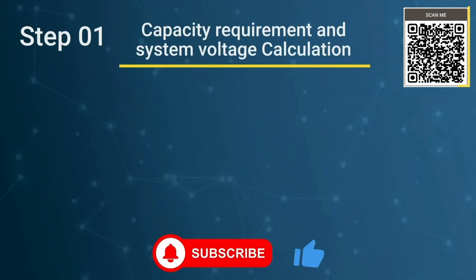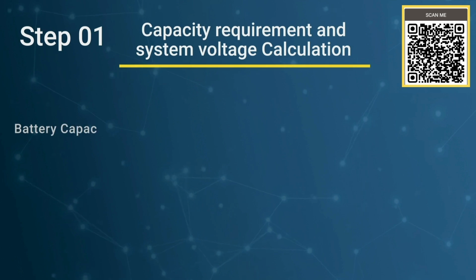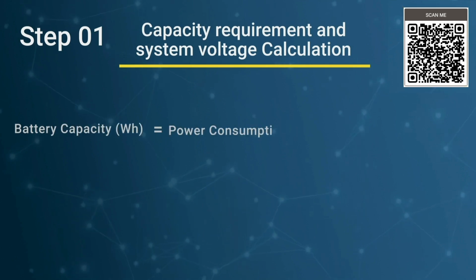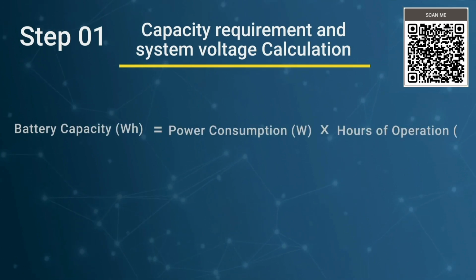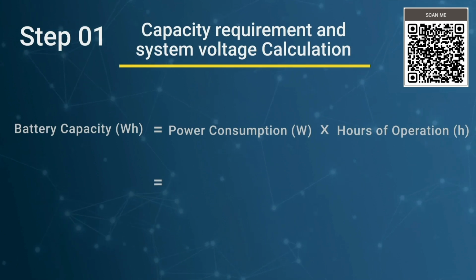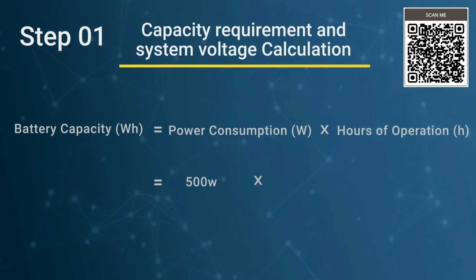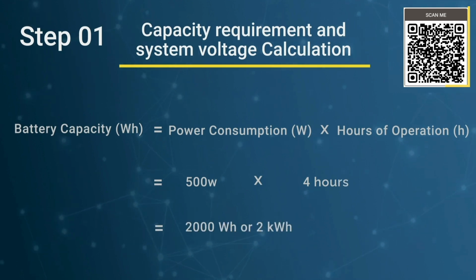First, we need to calculate the capacity requirement for the battery pack. Calculate the total capacity you need based on your application's power consumption. For example, if you need to power a 500-watt inverter at full load for 4 hours, you'll need a battery pack with a capacity of at least 2 kilowatt-hours.